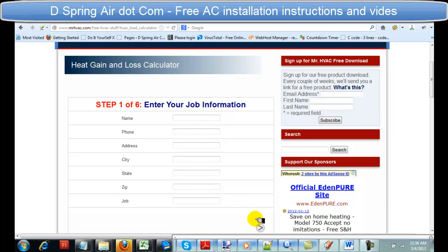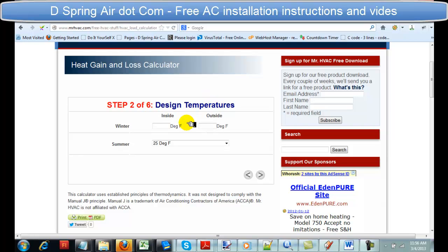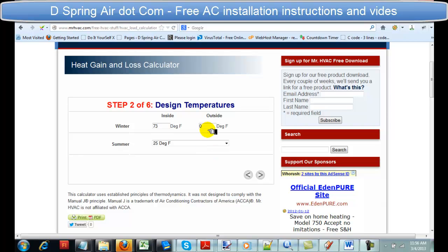Step one of six is to enter your job information: name, phone number, and everything. Step two of six is design temperatures. Inside degrees Fahrenheit is what you want in the winter time, and the outside is what the actual temperature is. Say you're living in New York and you want 73 degrees inside in the winter — the outside temperature, I usually go with the worst temperature, like minus 10. Put down zero, because who wants a furnace that doesn't work when it's minus 20?